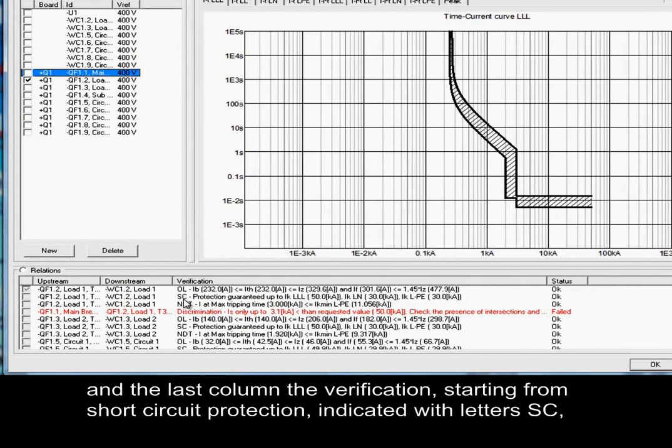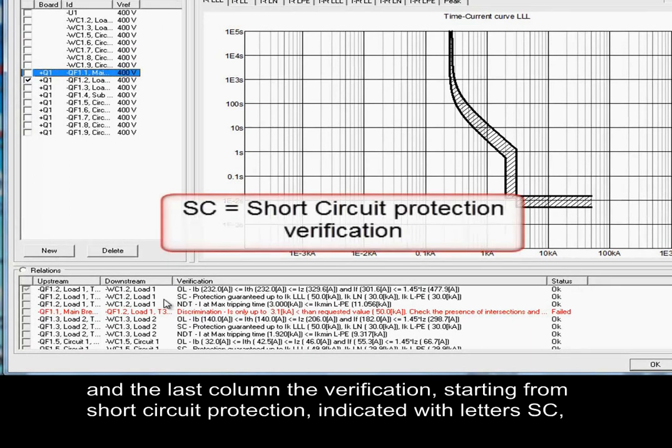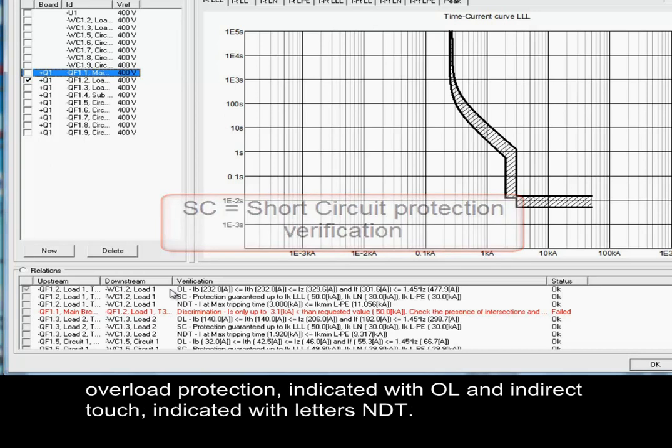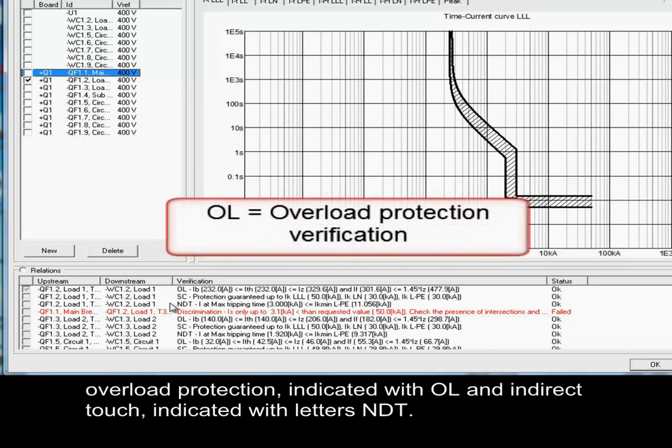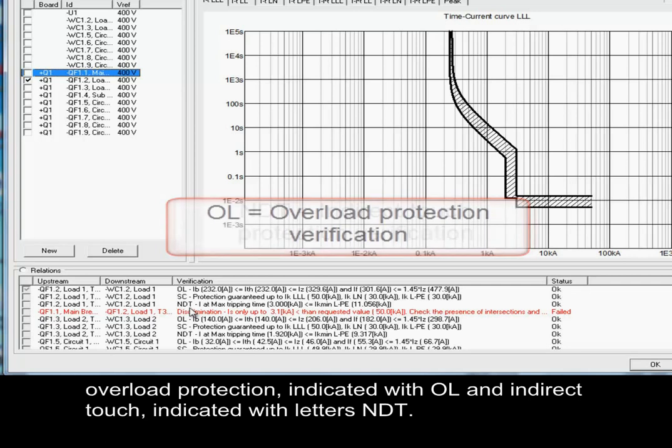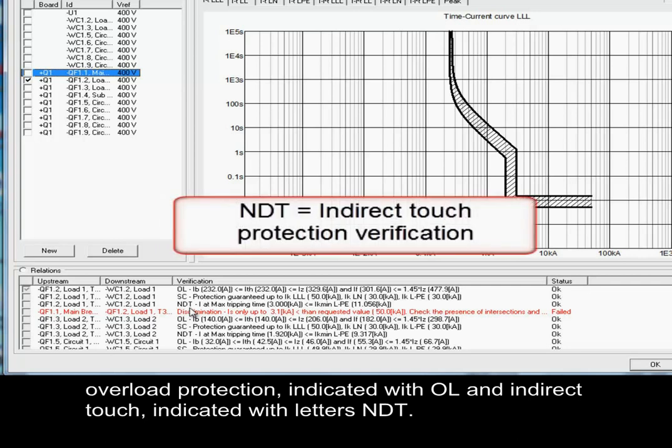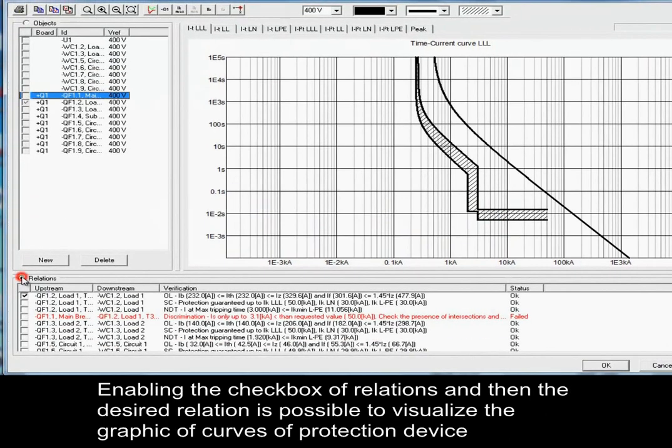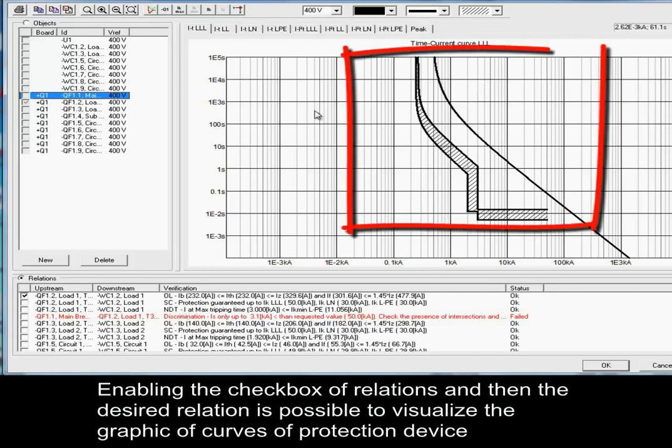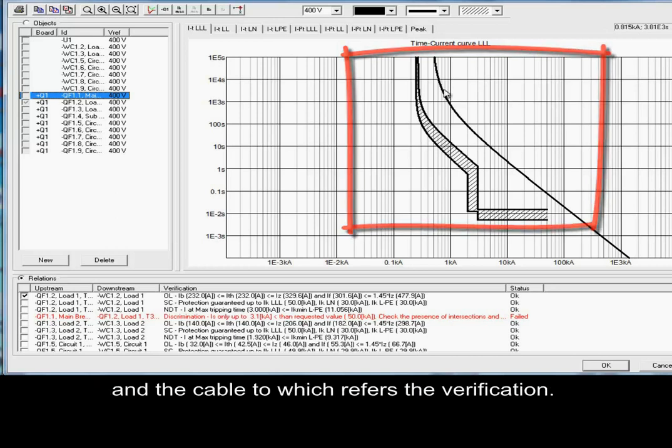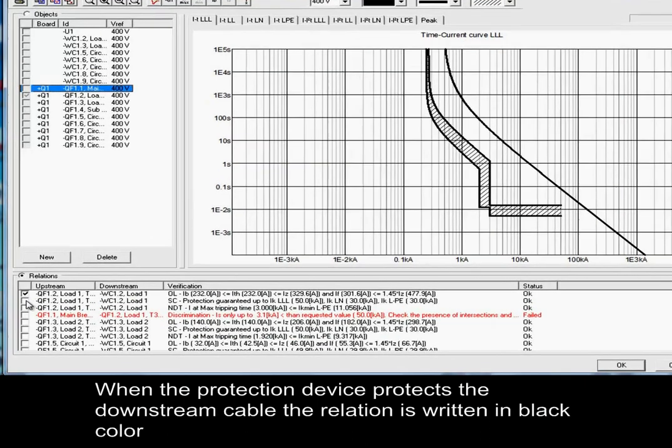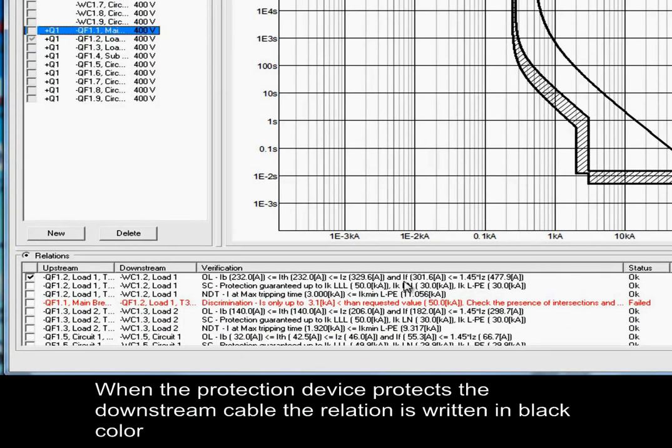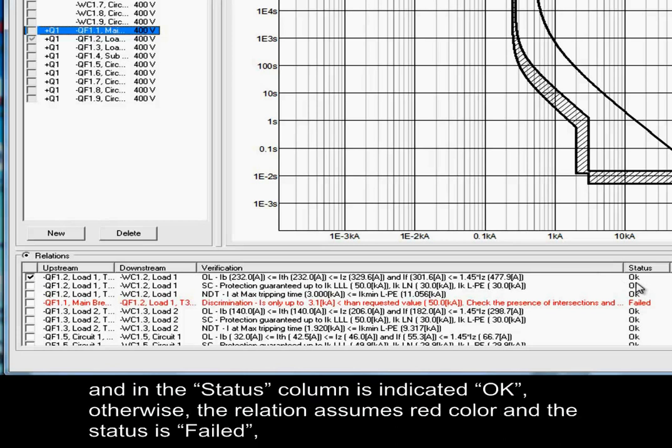Starting from short-circuit protection indicated with letters SC, overload protection indicated with OL, and indirect touch indicated with letters NDT. Enabling the checkbox of relations and then the desired relation, it is possible to visualize the graphic of curves of protection device and the cable to which refers the verification. When the protection device protects the downstream cable, the relation is written in black color and in the status column is indicated OK.